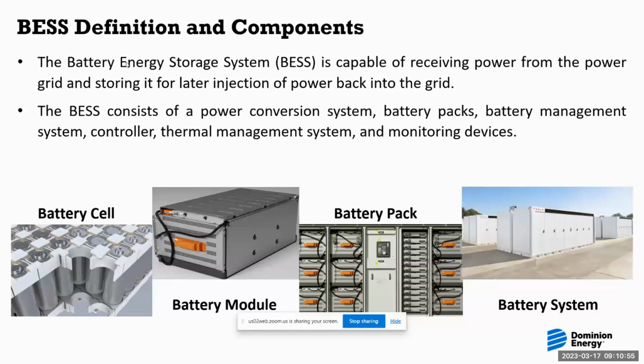The smallest component of a battery system is the cell, shown on the left. They don't look much different than cells you'd see in a flashlight, maybe a little bigger. Each is typically about 2.7 volts DC, and we string them together in parallel and series combinations to make about 1,000 volts DC, feeding that to the bidirectional inverter, also known as the power conversion system, to discharge onto the grid.